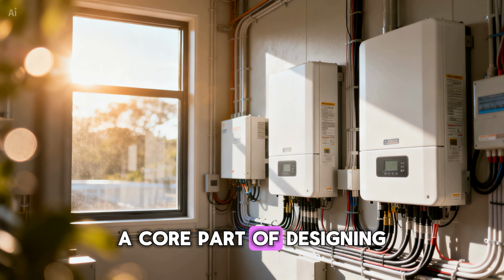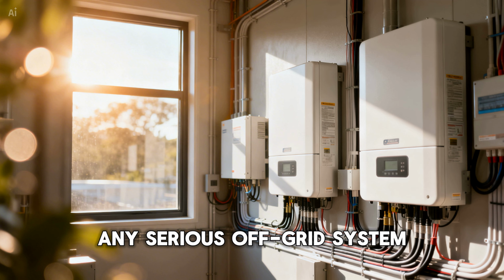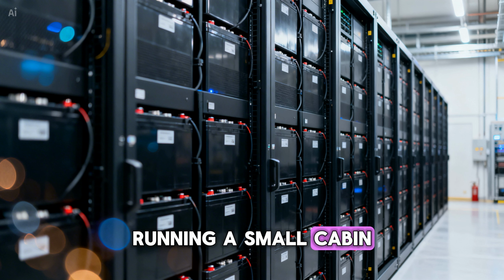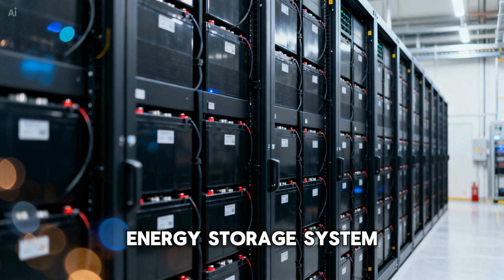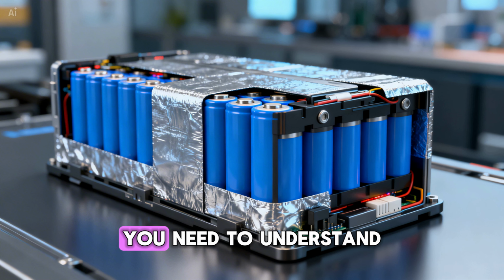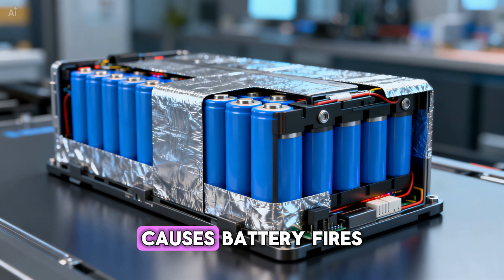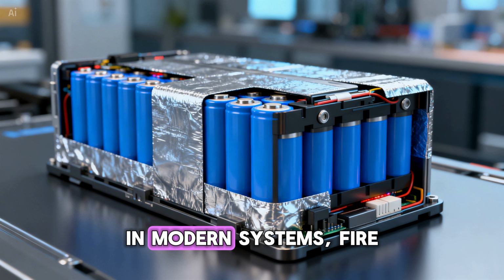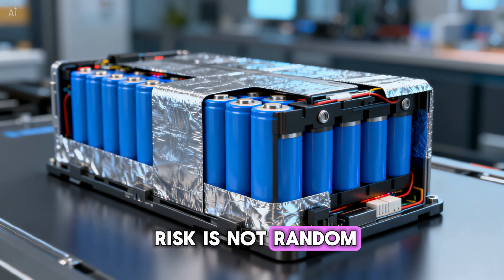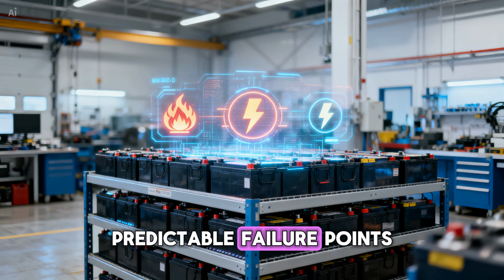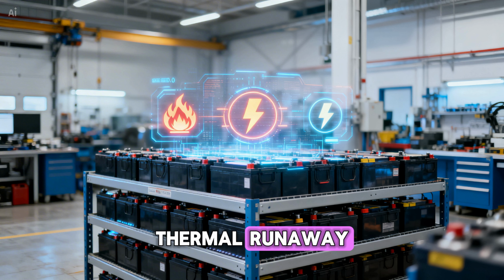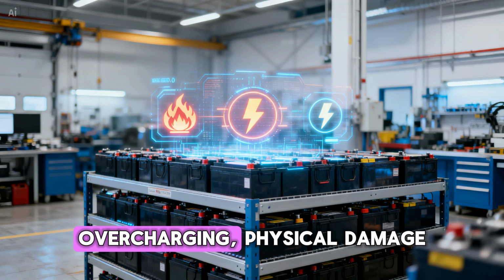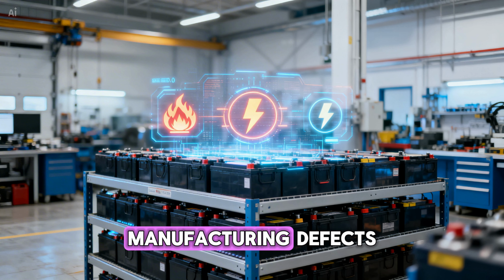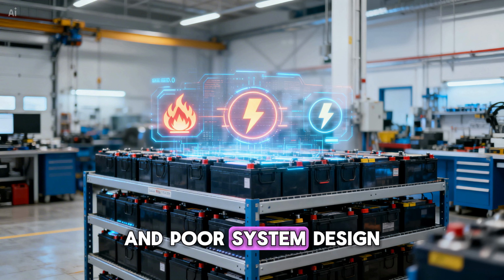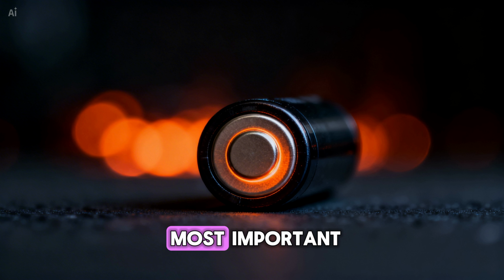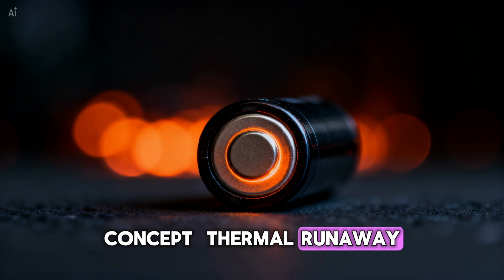It's a core part of designing any serious off-grid system, whether you're running a small cabin setup or a full-scale energy storage system. At the beginning, you need to understand what actually causes battery fires. In modern systems, fire risk is not random. It comes from a few predictable failure points: thermal runaway, electrical short circuits, overcharging, physical damage, manufacturing defects, and poor system design. Let's start with the most important concept: thermal runaway.